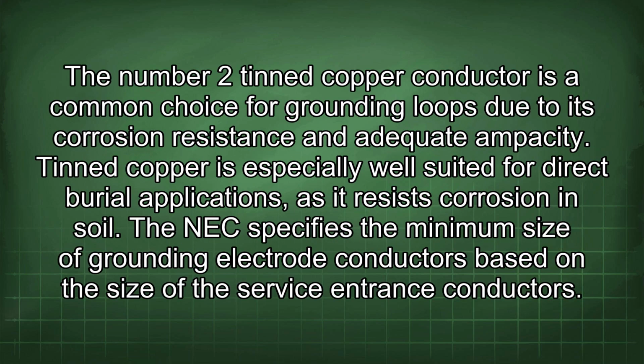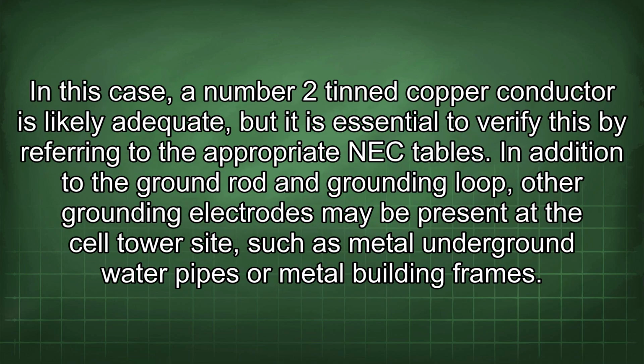The number 2 tinned copper conductor is a common choice for grounding loops due to its corrosion resistance and adequate ampacity. Tinned copper is especially well suited for direct burial applications as it resists corrosion in soil. The NEC specifies the minimum size of grounding electrode conductors based on the size of the service entrance conductors. In this case, a number 2 tinned copper conductor is likely adequate, but it is essential to verify this by referring to the appropriate NEC tables.